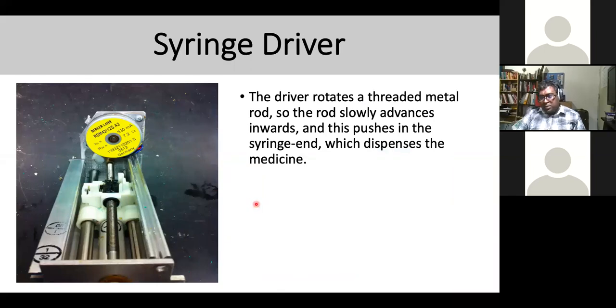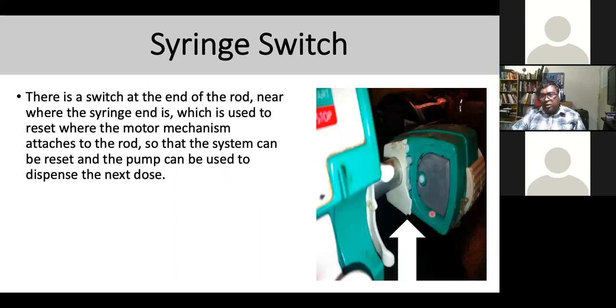And the syringe switch, the black one with the small knob with the green, all that. You can see where the switch reacts to the syringe itself. When you put in a syringe, it's going to activate that switch, and when you key in the information, it will tell you what type of syringe you are using. Is it 60 ml, all that? Because when you pull, that's a signal indicating the size of the syringe. When the switch at the end of the rod is near the syringe, it will reset the motor mechanism. So this is how the syringe switch works.